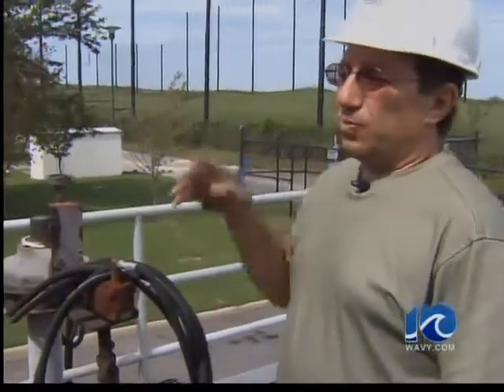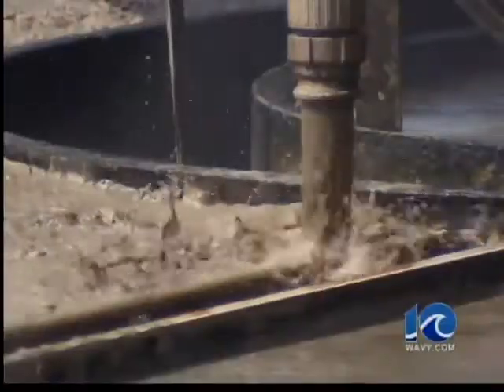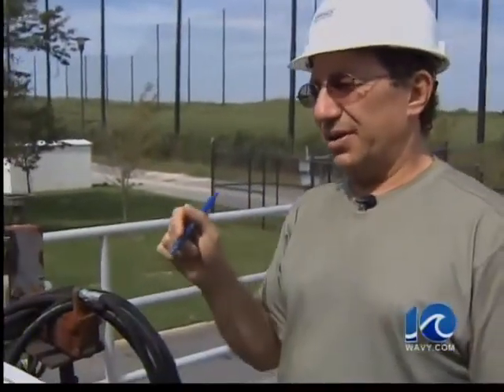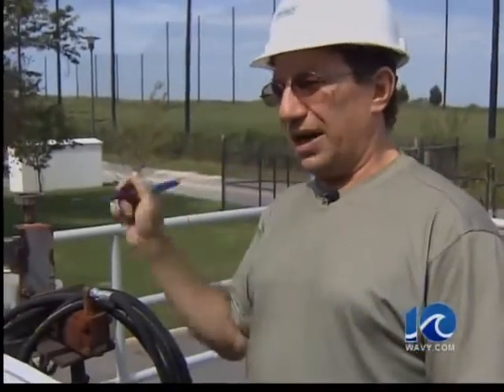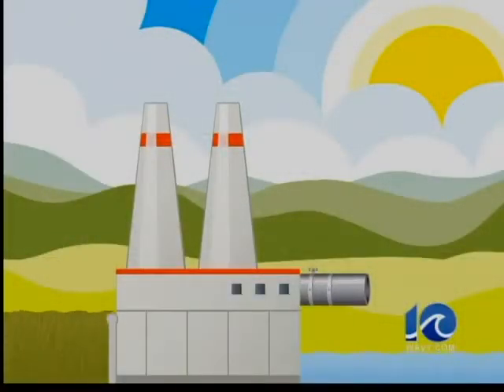Fearing a power outage from the Wednesday storms, Gosen put the system on generator so the wastewater would continue to be pumped to these treatment tanks. When we did, the generators failed, and a safety mechanism did not allow us to go back to utility power. So no generator and no electricity and no pumping going on. Raw sewage backing up for 27 minutes.